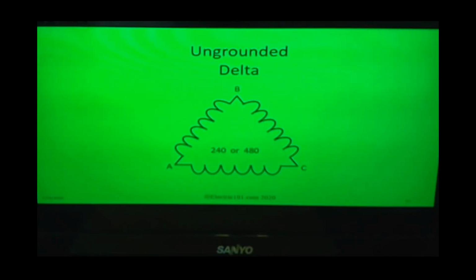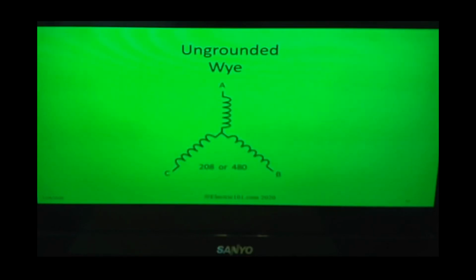Now, in this circuit right here, for example, you measure between A phase and B phase, I might get 480. B to C, 480. A to C, 480. So this would be 480 volt three phase. Now on the other side of that coin, a lot of these transformers are only 240 volts. So I would measure 240 volts, 240, and 240. Point is, when you have an ungrounded system, all you're going to measure is one voltage. Only one.